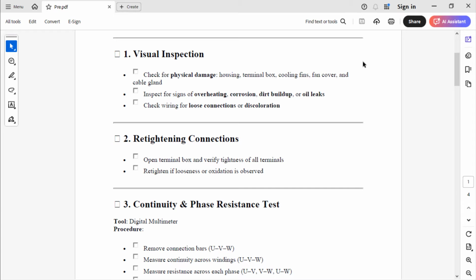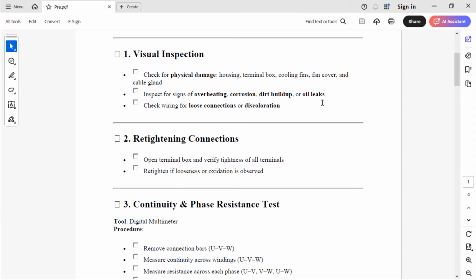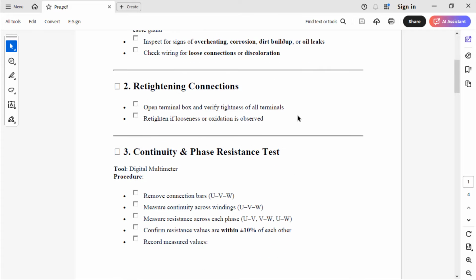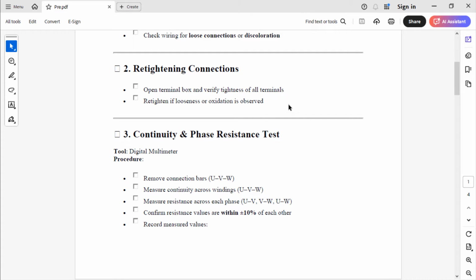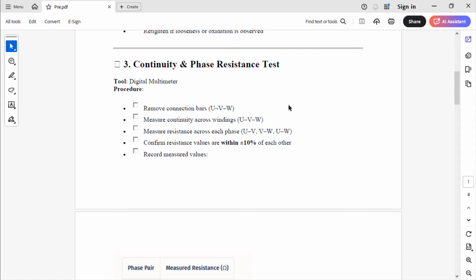Let's start with a visual inspection of the motor. Here we check for physical damage like the housing, terminal box, cooling fins, fan cover, and cable gland. Also, we inspect for signs of overheating, corrosion, dirt buildup, or oil leaks. After that, we check wiring for loose connections and discoloration. So we retighten connections if needed. We open the terminal box and verify tightness of all terminals. Retighten if looseness or oxidation is observed.